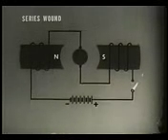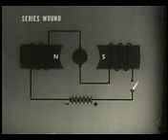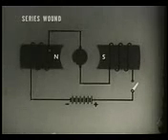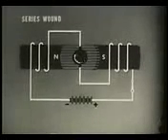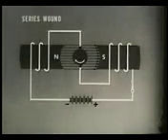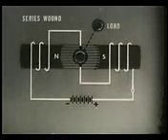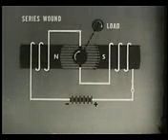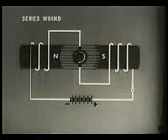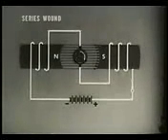Since field strength is proportional to current, the high starting current before CEMF is developed affects torque as the square of the current. The motor begins to turn, attempting to develop enough CEMF to completely oppose the applied EMF. The load prevents this, acting to control the speed of the motor. But if the load is suddenly removed, like in the case of a broken belt, the motor will build up speed, trying to develop more CEMF until it destroys itself.